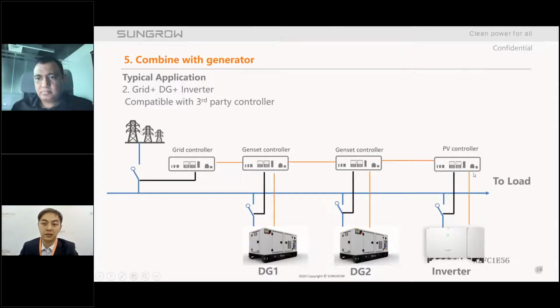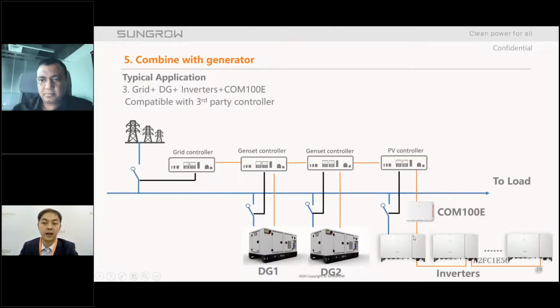The controller communicates directly with our inverter. Some people may ask, if I have multiple inverters, how can I control the power of the whole PV plant? For this, you can use the controller to connect with our monitoring device, the COM100E. With this application, you connect the controller with our monitoring device, and the monitoring device can control the whole PV plant - multiple inverters all controlled by one controller.